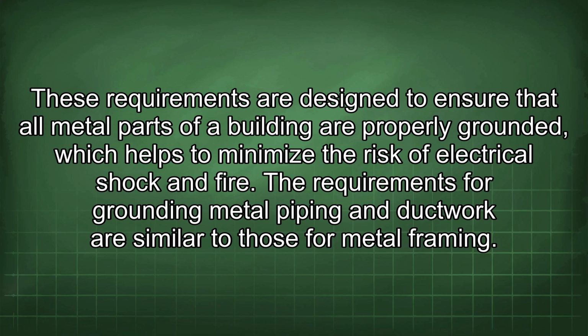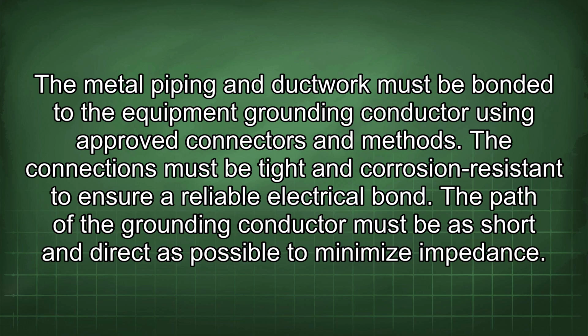The requirements for grounding metal piping and ductwork are similar to those for metal framing. The metal piping and ductwork must be bonded to the equipment grounding conductor using approved connectors and methods. The connections must be tight and corrosion resistant to ensure a reliable electrical bond. The path of the grounding conductor must be as short and direct as possible to minimize impedance.